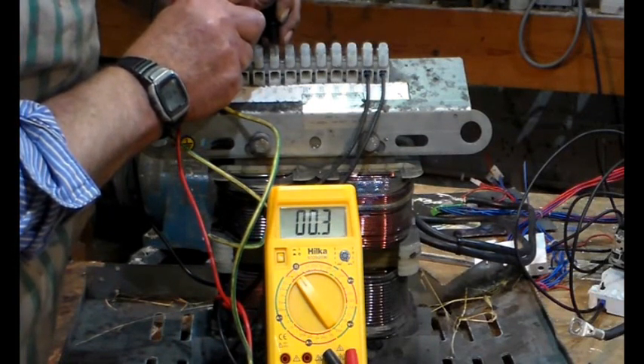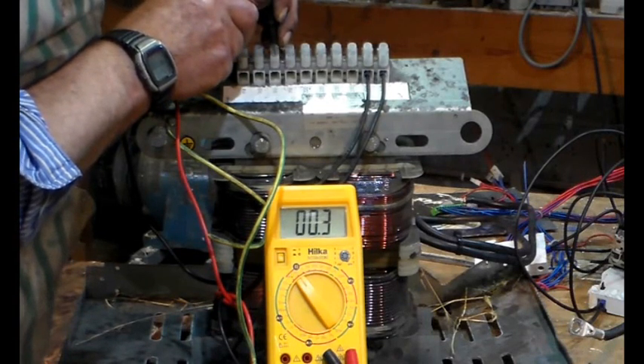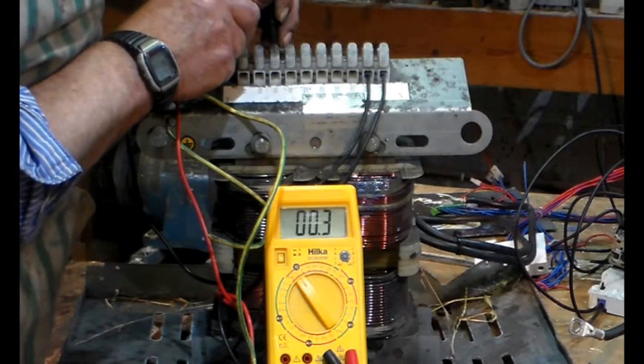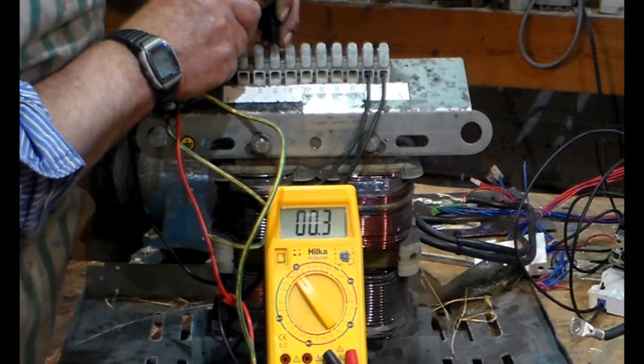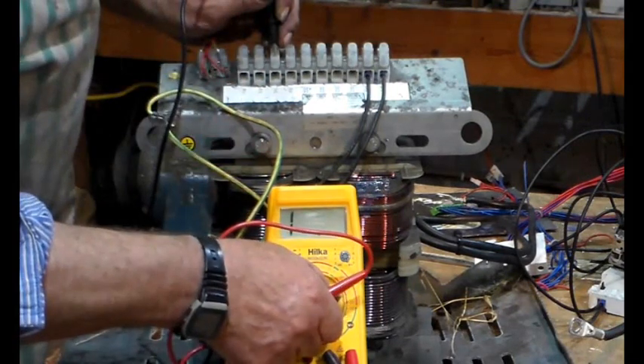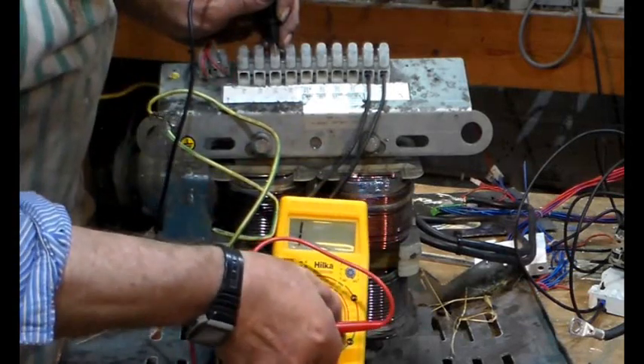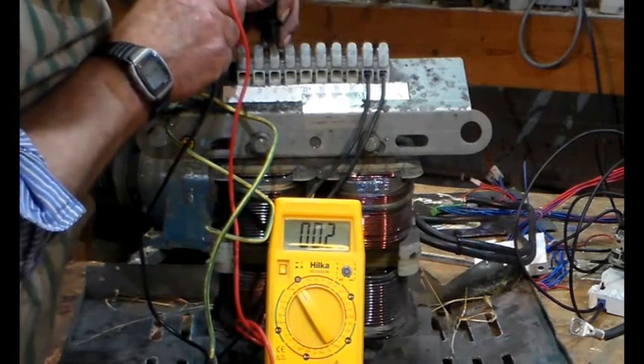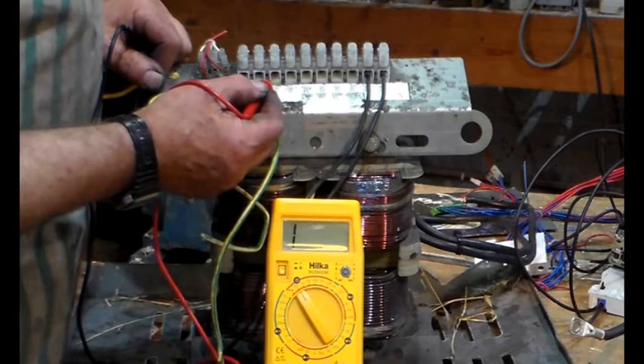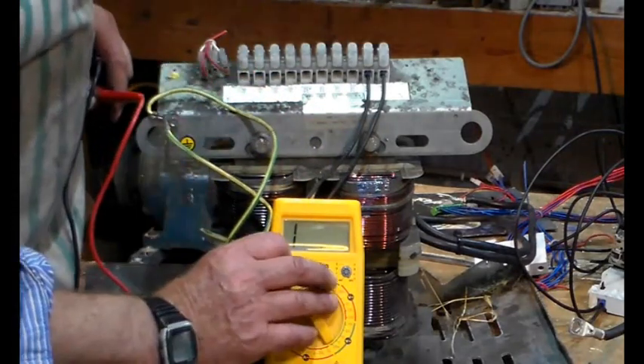These effectively, what are neutrals? They're not the same. W O and W A will affect the voltage out on the low voltage side. If we go to W A, there's slightly more coils in there because there's 0.3 ohms. That's virtually a dead short but not quite.